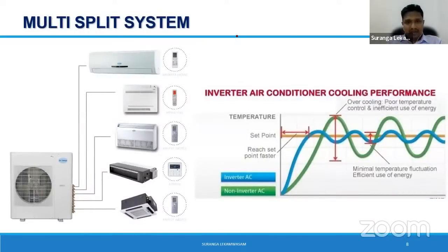Then on top of that, we have a system called the multi-split system. These are very popular in apartment buildings, vertical buildings, because when you have apartments, you may need multiple indoor units. There is no space to locate multiple outdoor units because the footprint is pretty expensive as you go higher and higher. The choice was to go for a multi-split system, where you can connect multiple indoors with a single outdoor condenser, right? That is very popular in apartment buildings and proven in the industry for the last couple of years. It looks like this. You can see this is your condenser connected with multiple indoors. Special features: you can see there are different refrigerant pipes, supply and return. You have to lay them separately for each and every indoor unit.